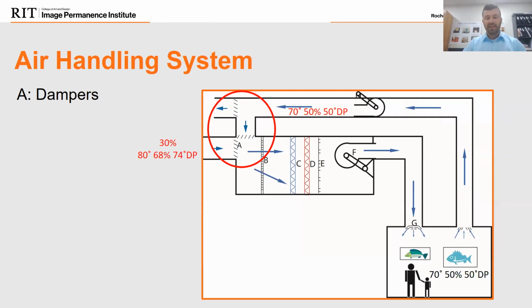So next stop on the air handling system. We brought that air through. As I discussed earlier, we pulled that air in from the room. Our air in this ductwork, assuming everything's perfect, we haven't lost or had any change of condition to that air in the ductwork. We brought that air back. We're at 70-50. What we're going to do now is exhaust a little bit of that air. We're going to return a little bit of it, and we're also going to bring in some outside air, and we're going to have some mixing of that air done here.